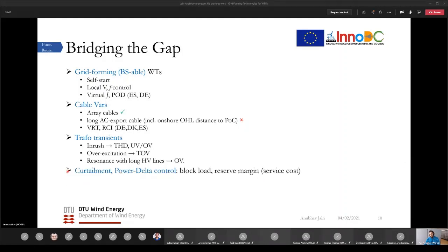One important thing is that during this energization, since there is no load before reaching the onshore step load, the main load that the wind farm has is the auxiliary load of the offshore substation, the HVDC substations, and its own wind farm load, which is not much. So there is an inherent curtailment, or derated operation, of the wind turbines for some time till the energization is complete.